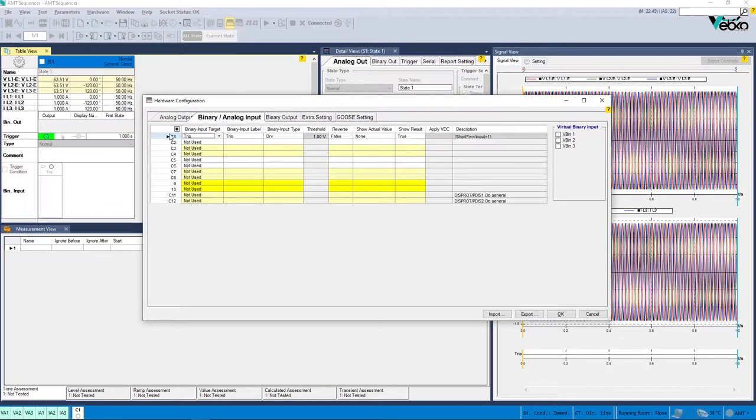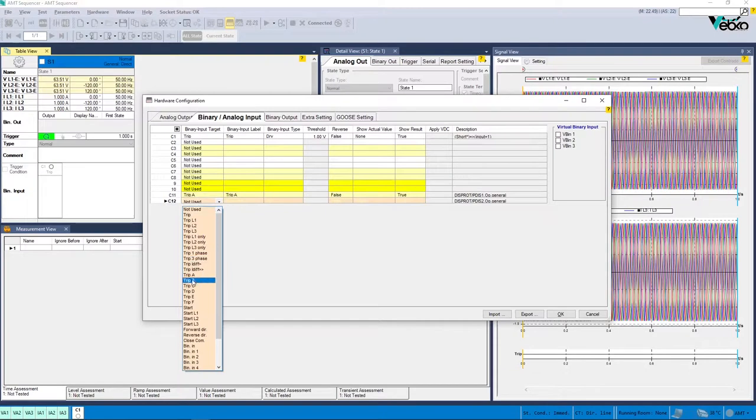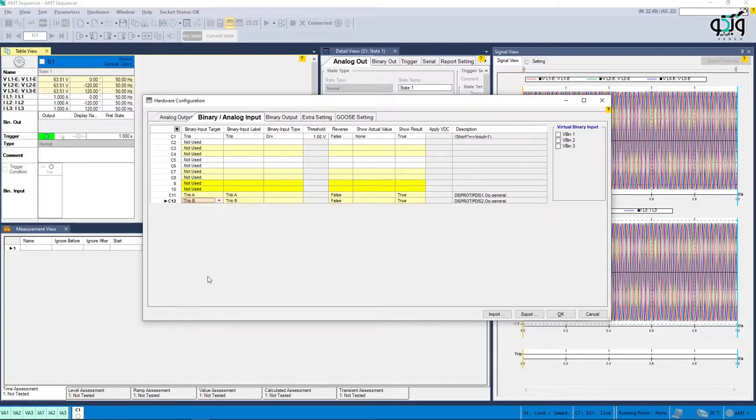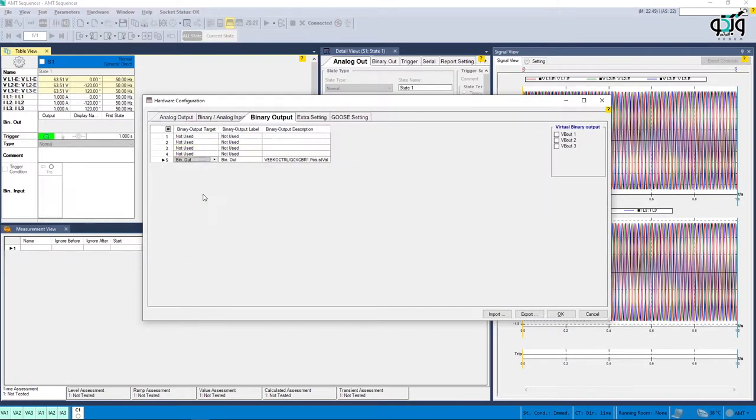In the next step, you need to set the configuration for binary inputs. Here, trip A and trip B are selected to record the relay performance against trip zones 1 and 2 respectively. Then, it is time for binary output to be configured. Clicking OK will save the settings. Now it is time to do the test.